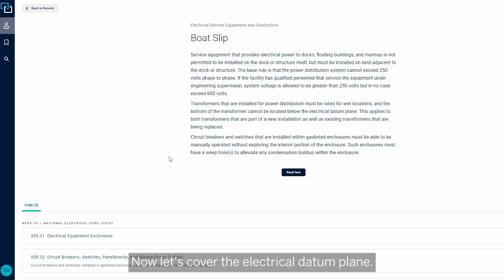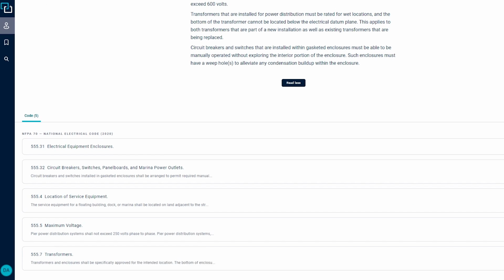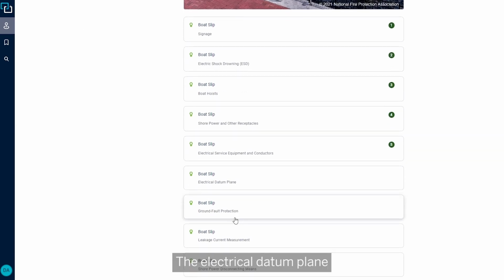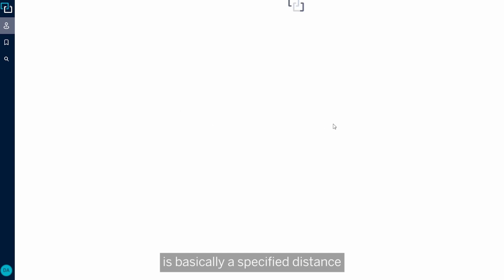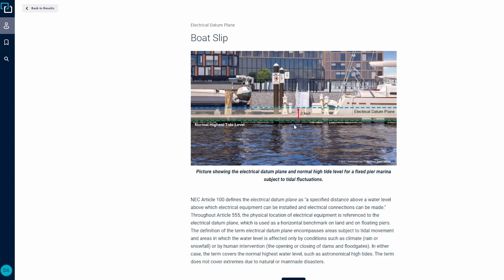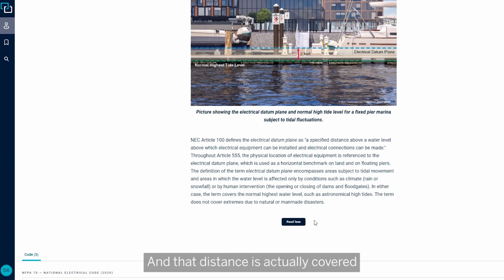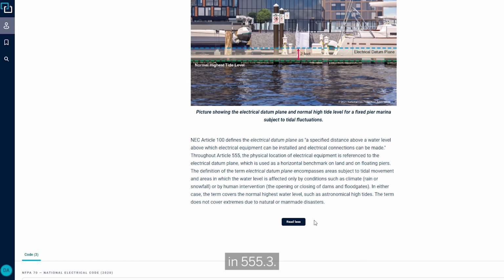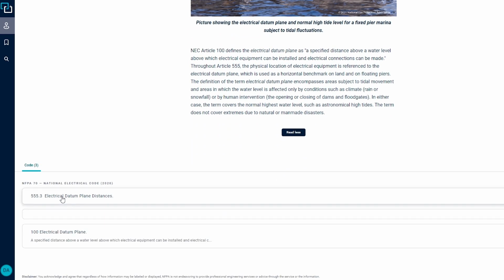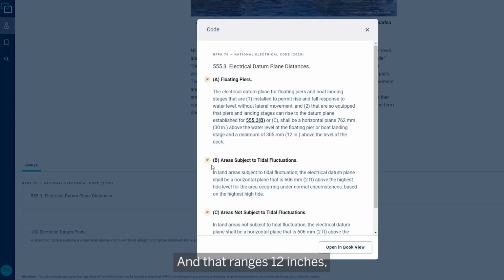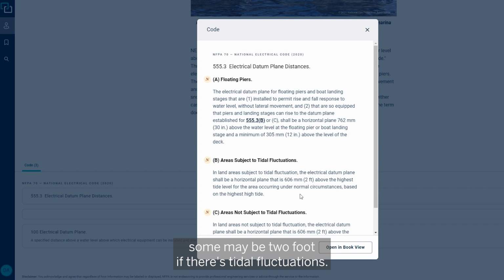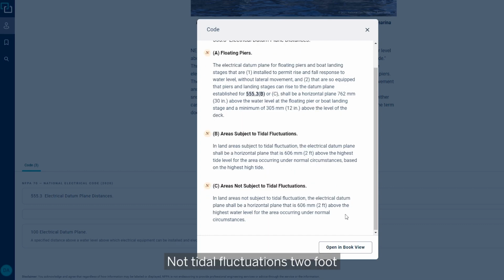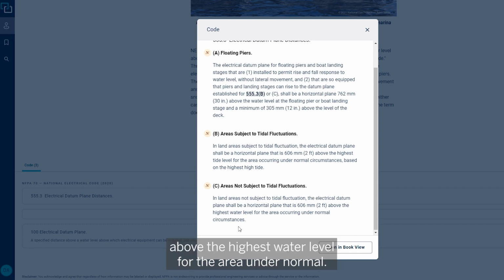Now let's cover the electrical datum plane. The electrical datum plane is basically a specified distance above the water. That distance is covered in 555.3. It ranges from 12 inches, and some may be 2 foot if there are tidal fluctuations, 2 foot above the highest water level for the area under normal conditions.